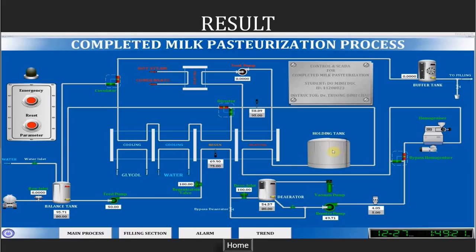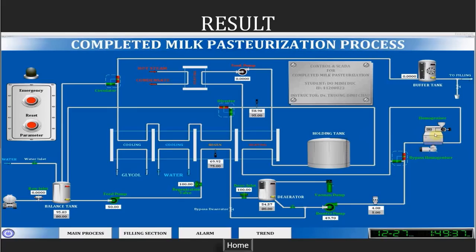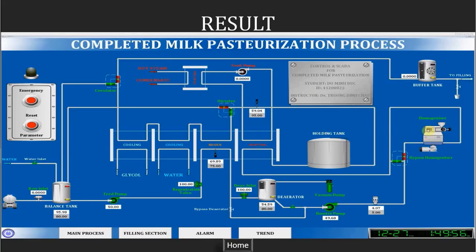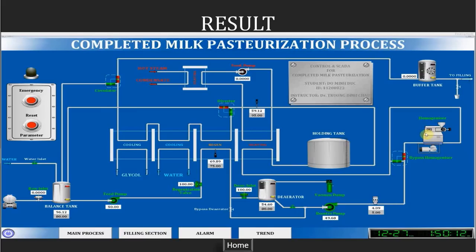This is a holding tank. It is designated to hold the milk in a specified time to completely kill all the bacteria. And this is a high pressure homogenizer. There are many valves and pistons in this device which will press the product to homogenize the fat and the milk together. Because there is always fat in the milk, and the fat may be curdled at the cooling section. It will clog the pipeline and raise the pressure in the line and will damage the process. This machine will work at a fixed flow rate and pressure condition which depends on the process capacity. That's why we need to control the pressure here.